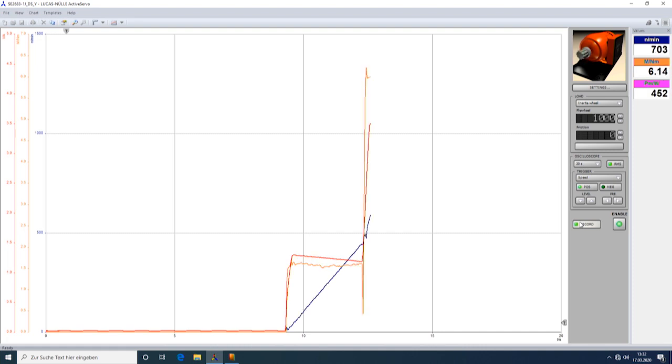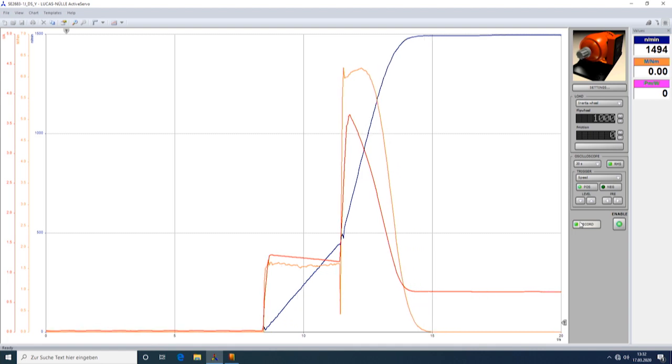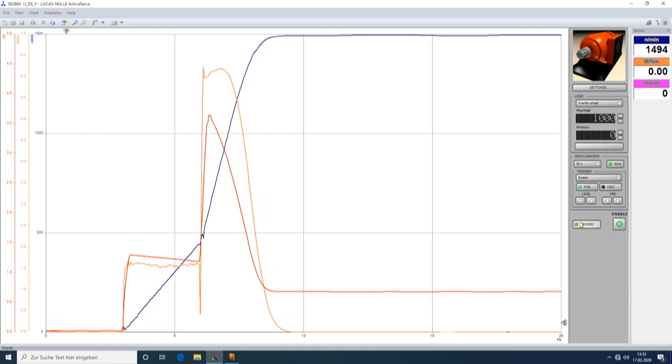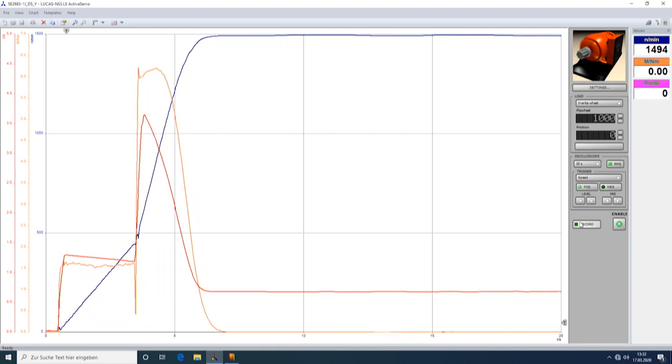Start, enable again, and press the record button. What we see here is that all the values are measured, and now I can start the motor in the next step. If I start the motor in the Y, see what happens, and then I switch to delta, and I can see directly the behavior. So we start here with a small current, then with a higher current when I switch to delta, and we see also the torque, which is given by the speed up of the system.